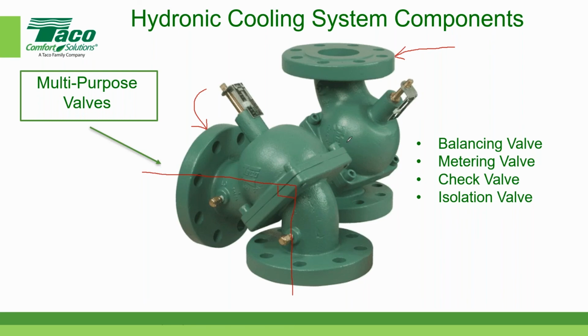And then you undo these four bolts on these flanges, and you can rotate it 180 degrees and turn it into a vertical, straight through multi-purpose valve. So it does four functions, and it also has the ability to act as both a 90 degree fitting and a straight through fitting. Isn't that cool, Brett? Yep, I think that's really cool. Field changeable too. Yeah, you can do that in the field. Just don't ruin the gasket. You'll need to put a new gasket on.